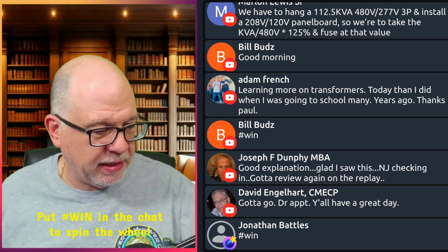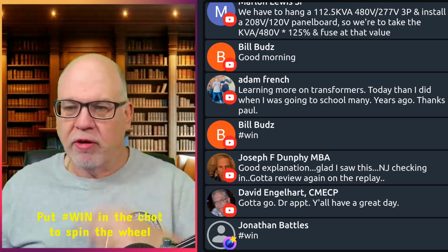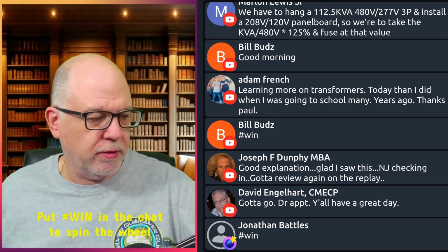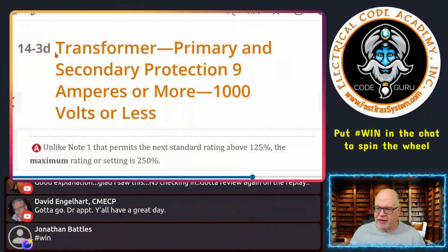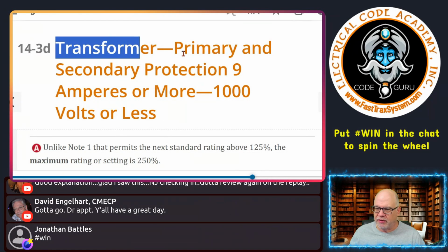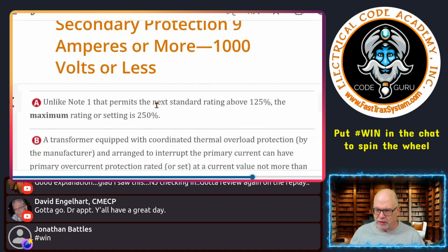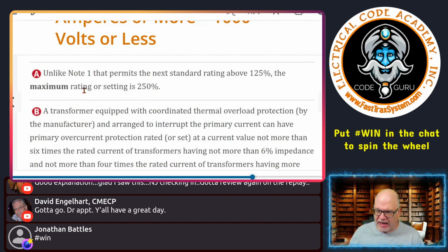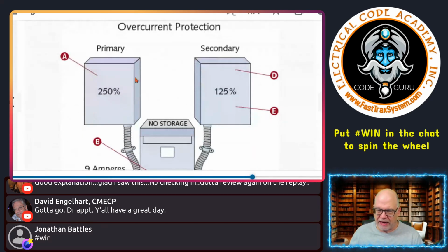The norm application. So here's the normal application for a transformer, primary and secondary protection, 9 amps or more, 1,000 volts or less type transformer. Number one is look at A. So A is right here. So why does this differ? So this differs because this one now has primary and secondary protection for that transformer. So you're going to be allowed to go up to 250% on the primary.